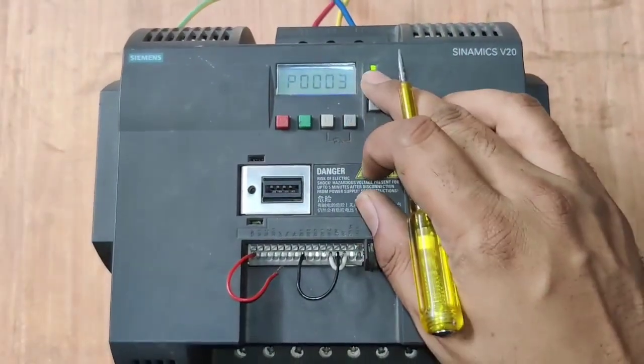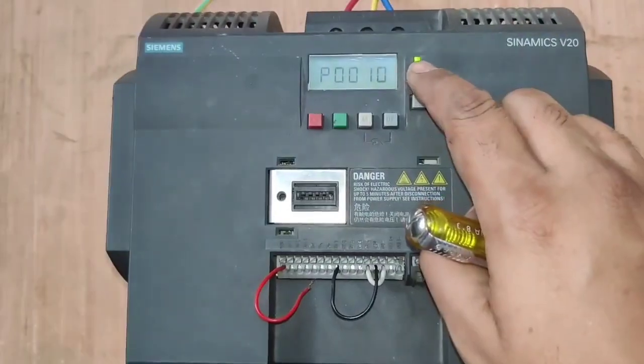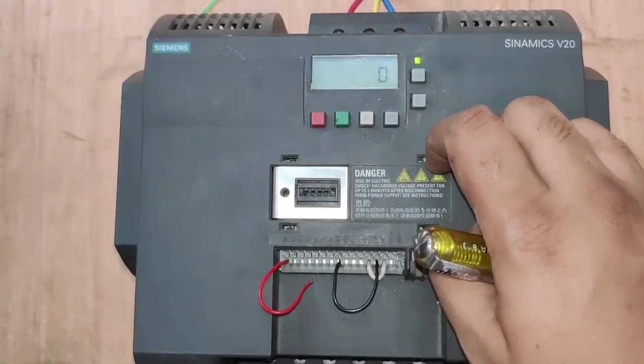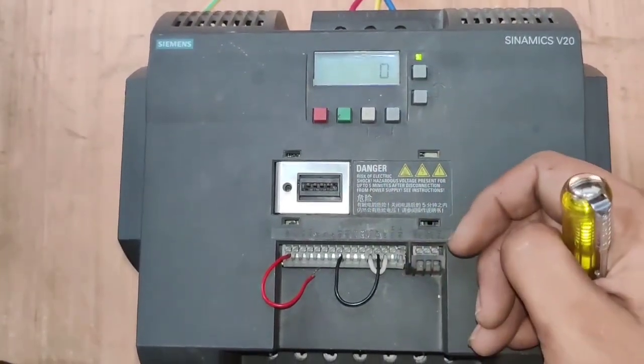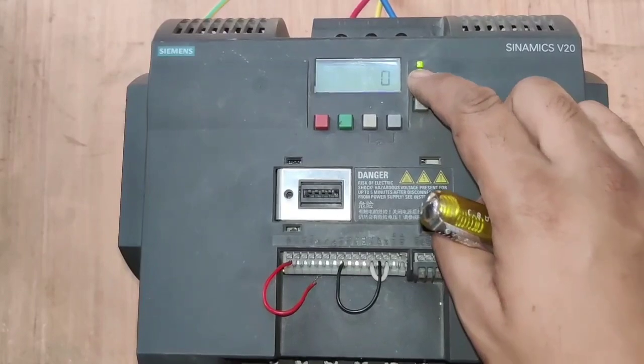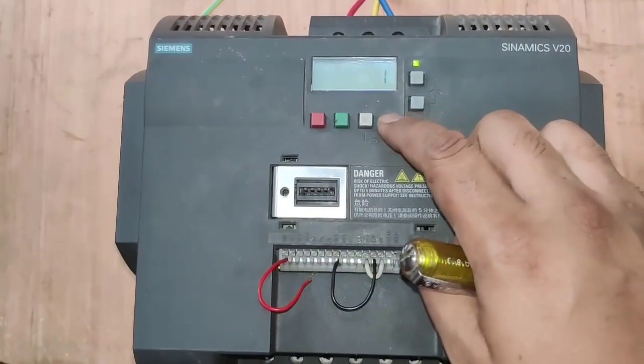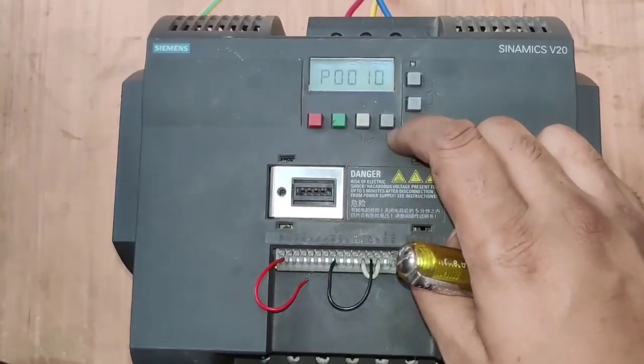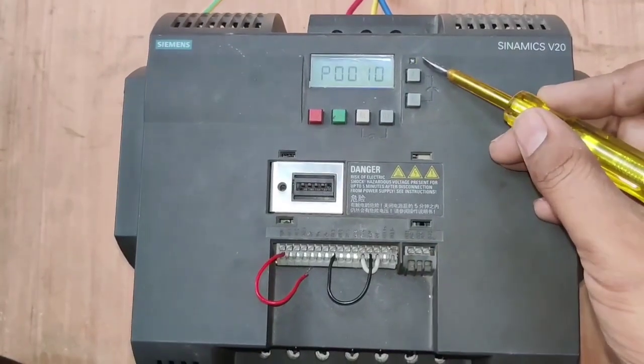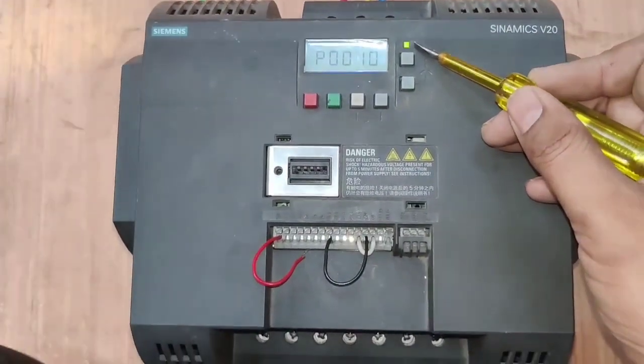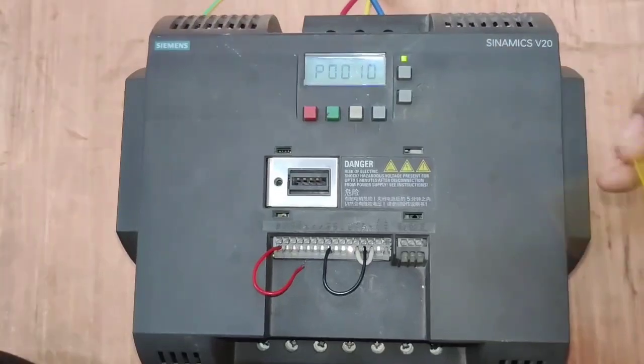Now the next parameter is P10. By up key, set P10. This parameter is for commissioning. Now you can see 0. If you set 0, that means the drive is in ready condition. For commissioning, our parameter setting, we set 1. You can see here for commissioning we set 1 and the LED is blinking. That means the drive is now in programming mode.